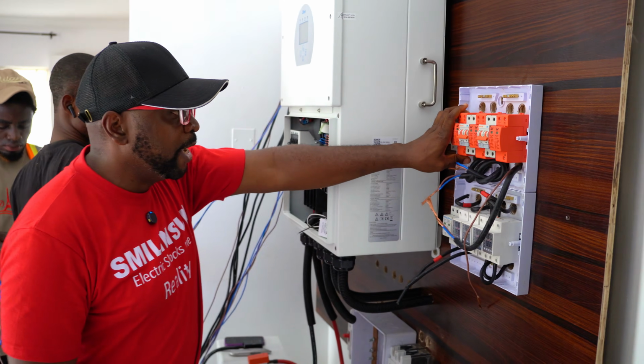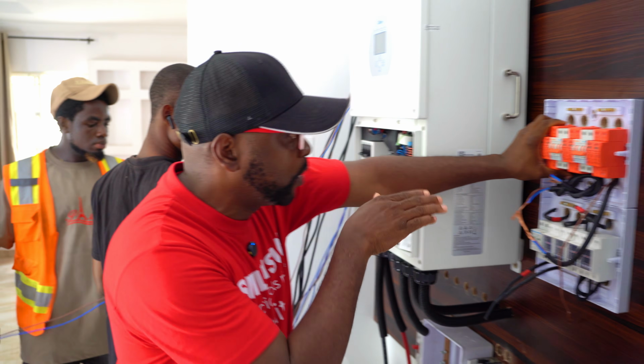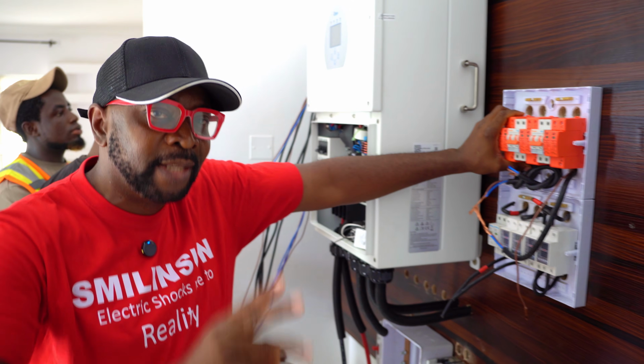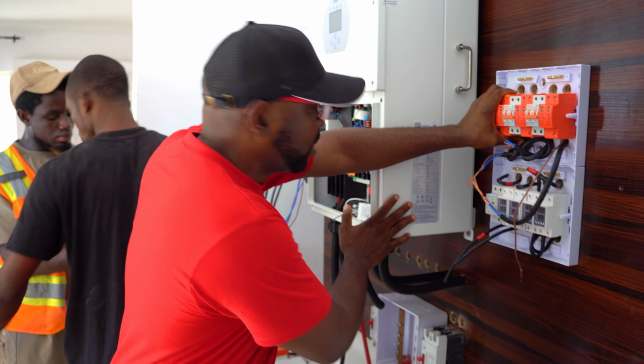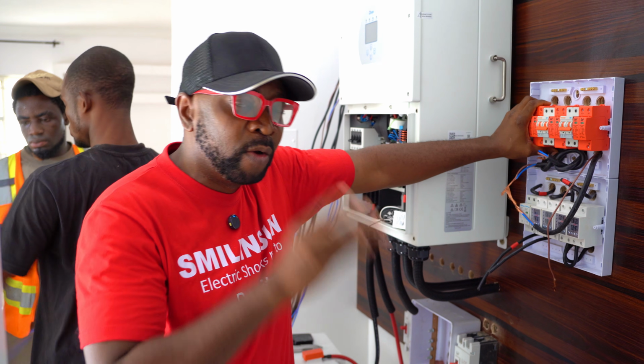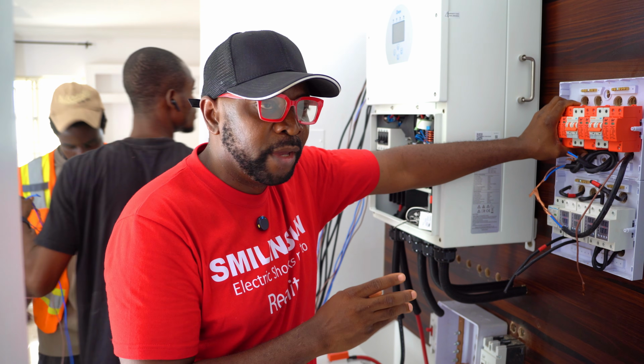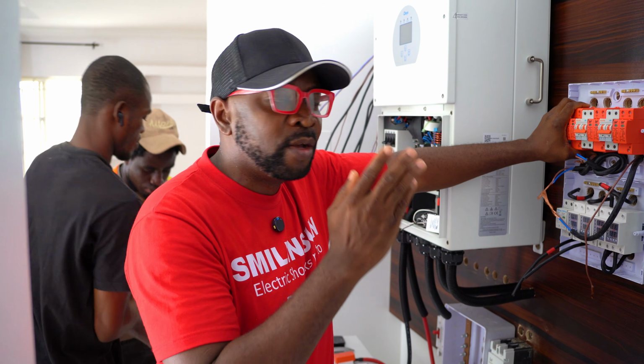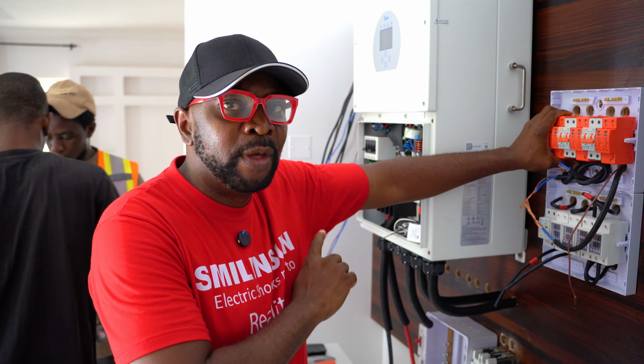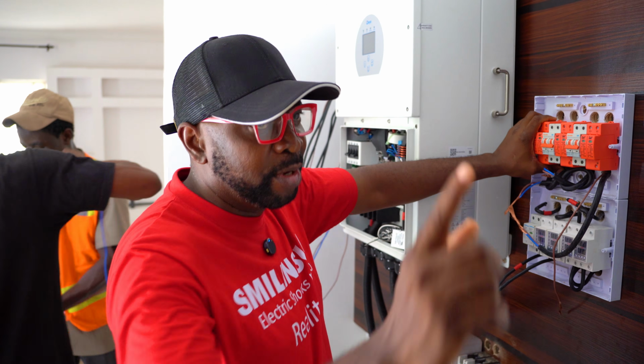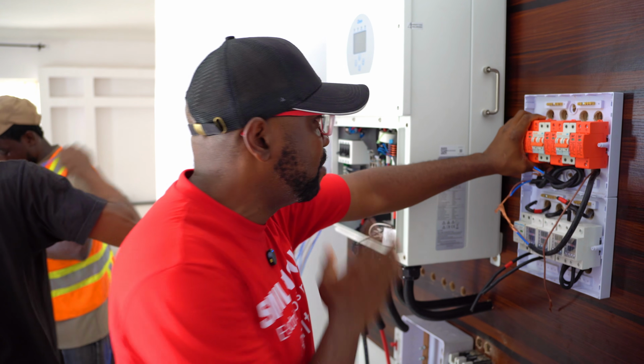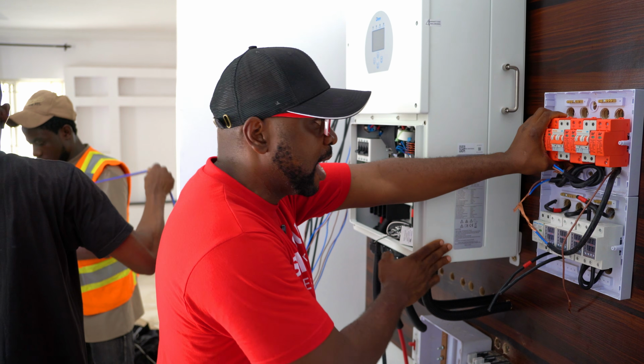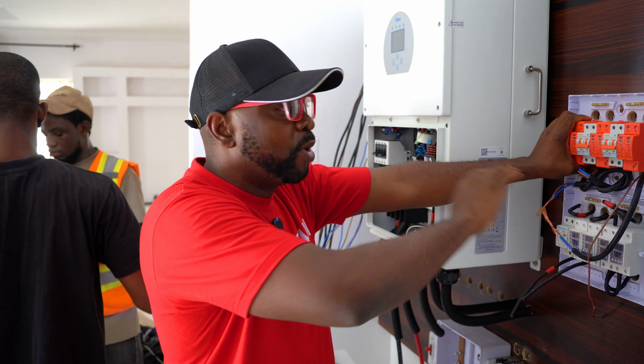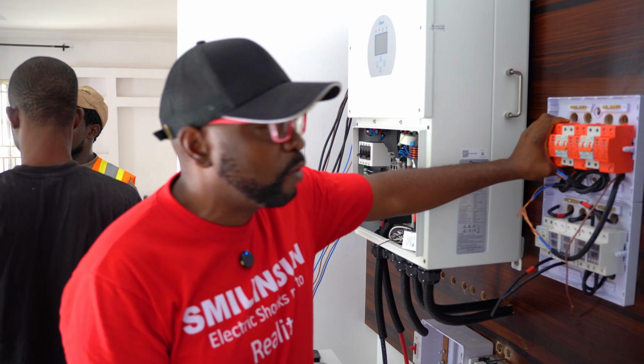Here is the surge protector and the circuit breakers controlling the PV. We're connecting 3 strings - this particular unit has 3 strings. We're going to connect the PVs in strings, in series and then parallel, because otherwise the voltage would exceed the maximum threshold of this unit. So here are all the circuit breakers and surge protectors for the PV.